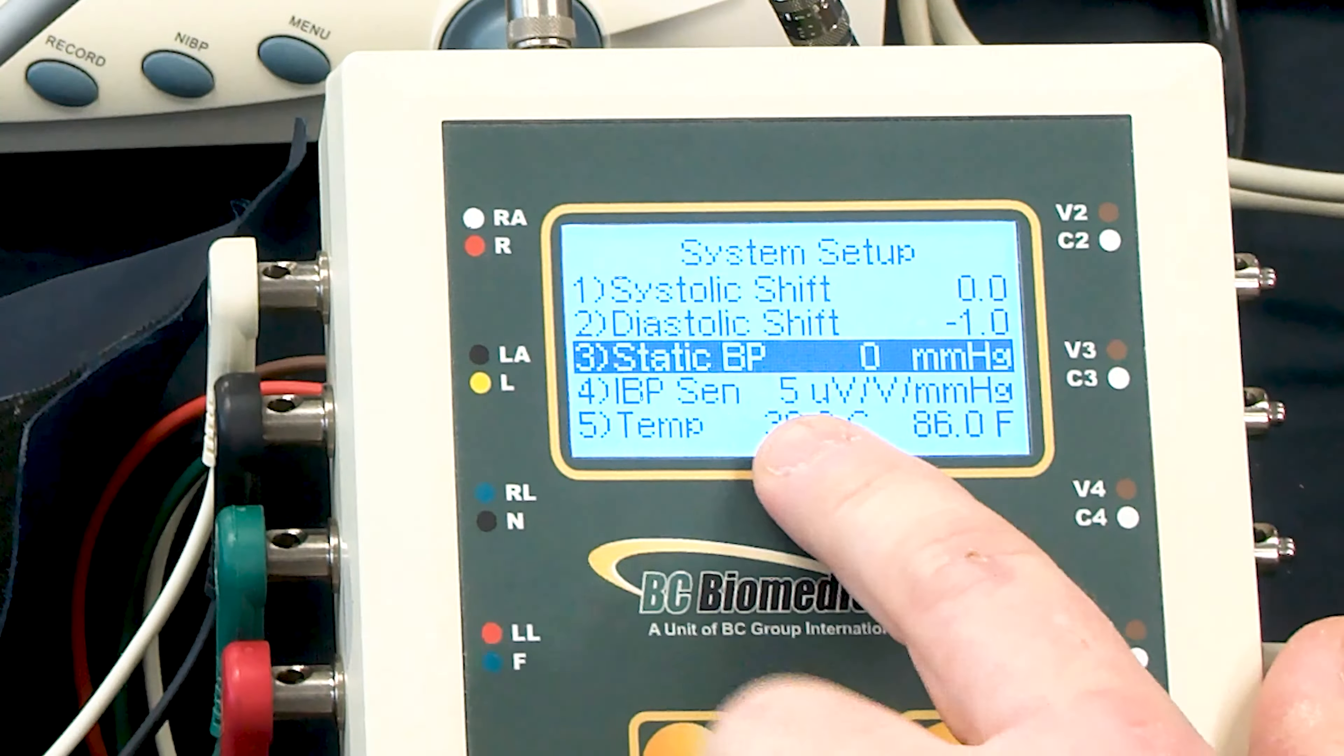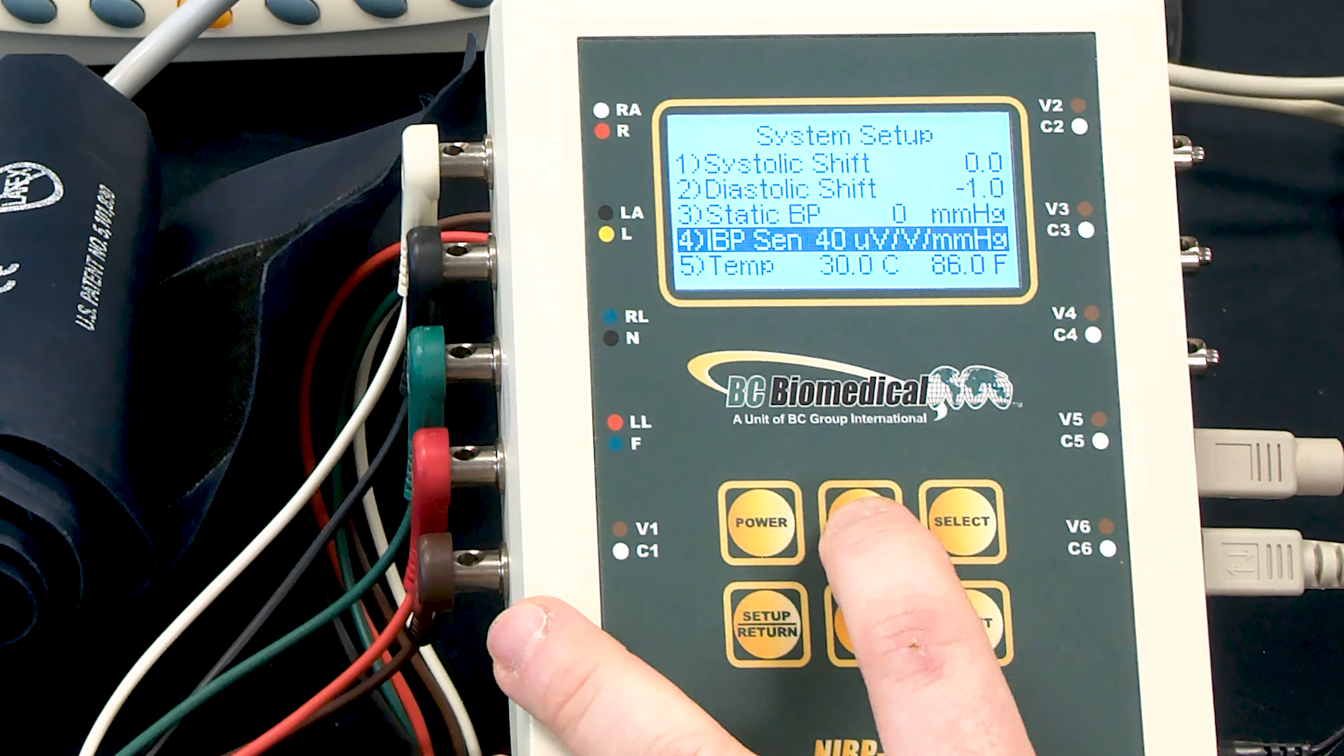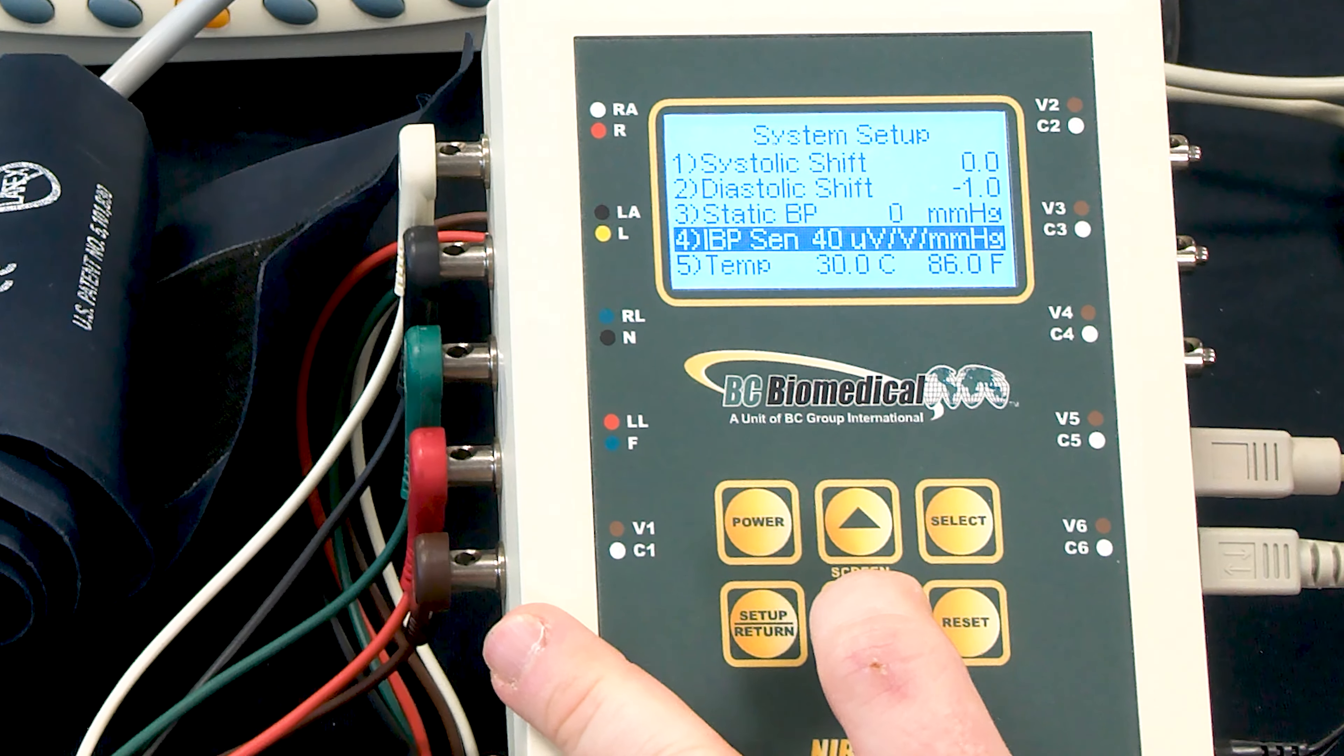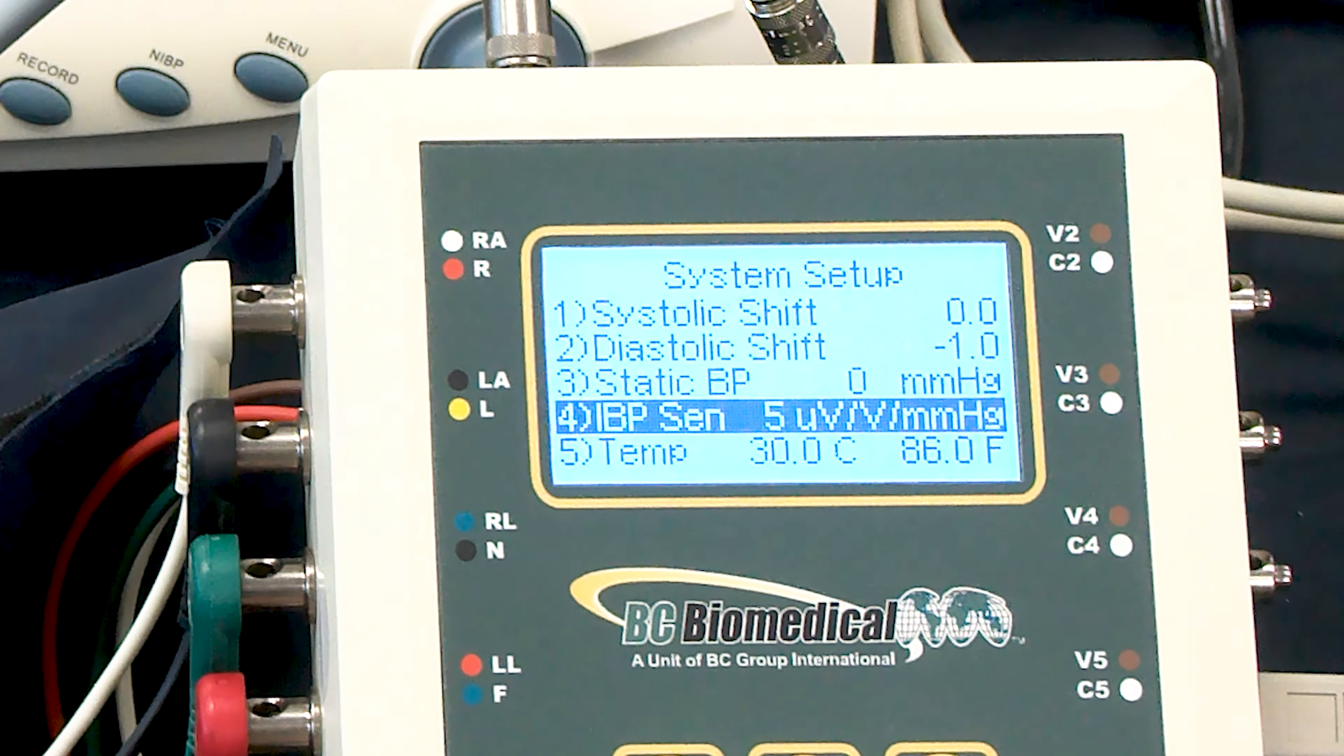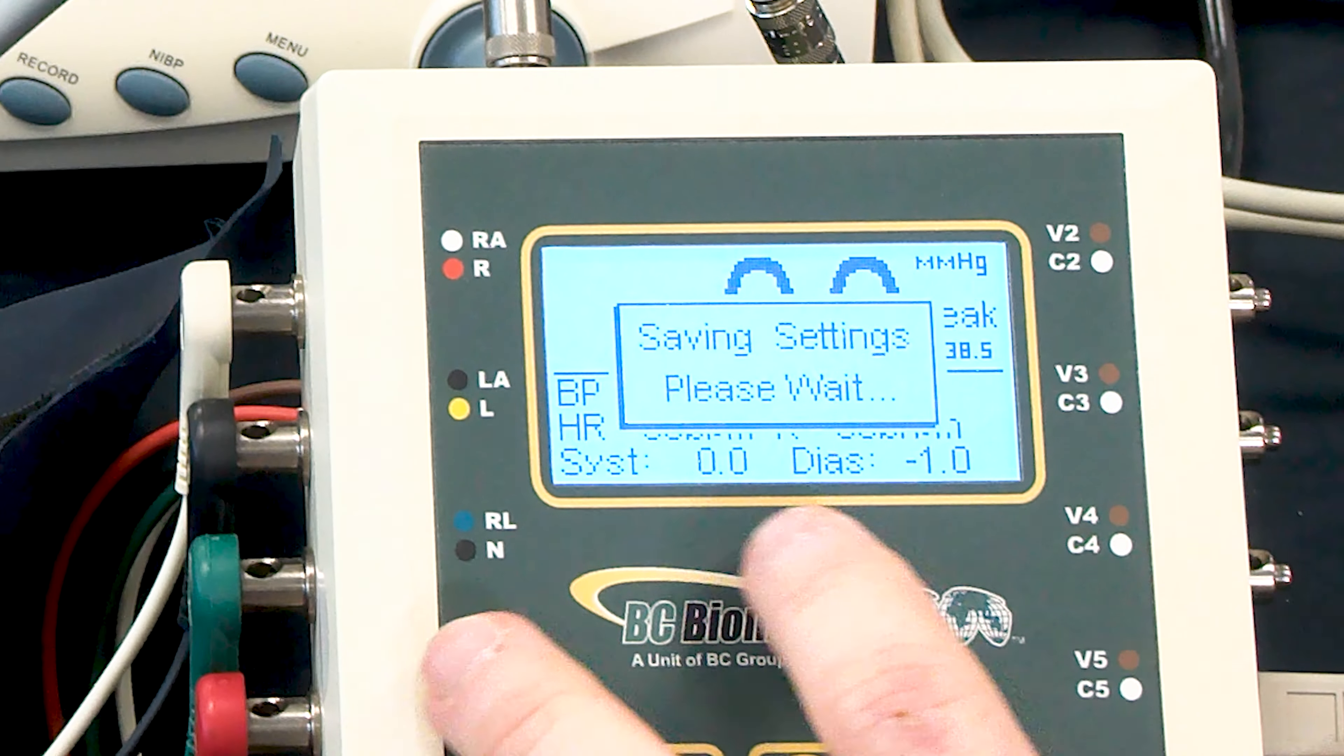The other thing that's important is the sensitivity. The NIBP has options for either 5 or 40 microvolts per volt per millimeter of mercury, and if that's not configured right, we won't get proper simulation on the monitor.